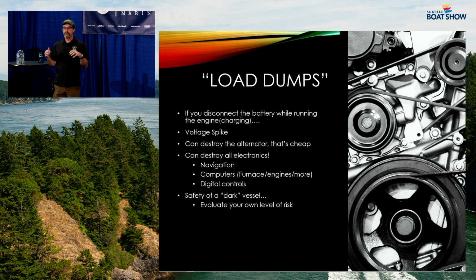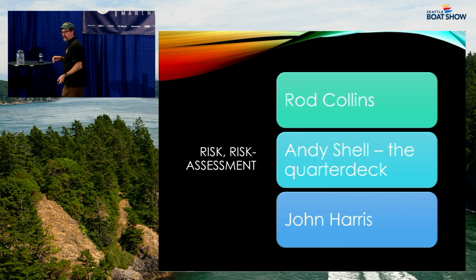By the way, there's a term out there that when I say the BMS disconnects, a lot of articles call that a load dump. I don't know why, it's a term that's stuck. If you're reading and hearing things, load dump just simply means we've got a fault of some sort and we are opening the contactor, saying we're taking this battery offline. If it's in a bank, just one going open is fine. If you only have 1 or 2 batteries and they open up, that's when it's not going to be fine.